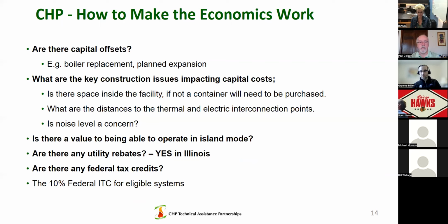For example, is there a facility expansion that this can be paired with to minimize dedicated construction costs? Are boiler replacements planned in the near future? That's a fantastic time to look at combined heat and power. Instead of spending this dedicated capital purchasing a new boiler, that boiler cost can be thought of as a credit towards CHP, whereas then the cost of CHP is only the marginal difference between the cost of a boiler and the full cost of a CHP system.